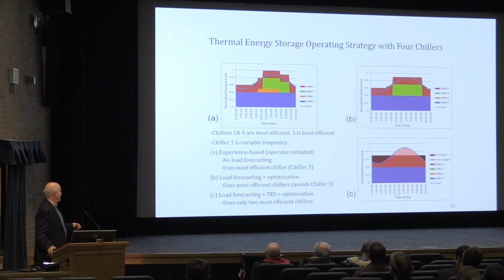Then if we bring in thermal storage, we get this case: here's the load again, and we've got essentially chiller 4 and chiller 1. Here's the load profile, but in these areas we're doing thermal storage, sending that to storage and using that to hit the peak.